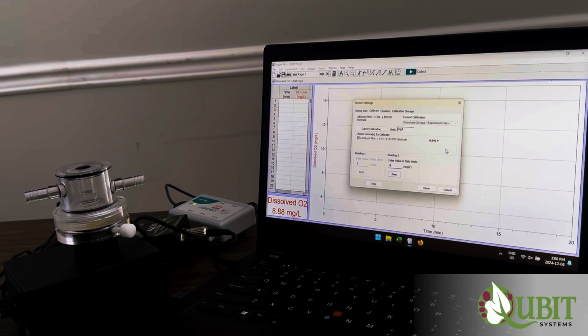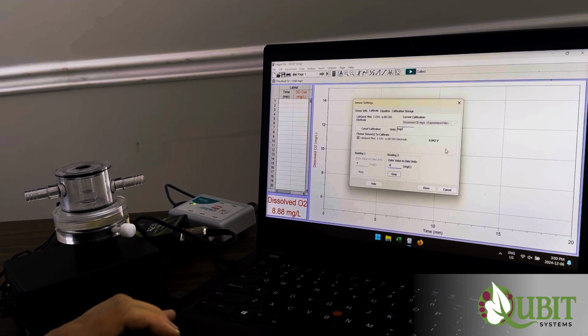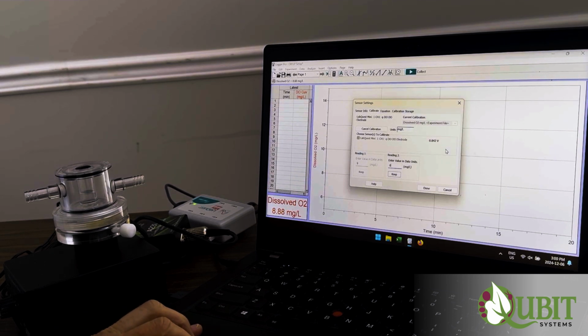And it's really important that you recalibrate the electrode every single time you set it up. Setting up the electrode at the beginning of the day of experiments is a good idea. Leaving it overnight once set up is possible, you know, with some distilled water. But if the next morning you come in and you find your readings are not very stable, erratic in any way, then we recommend that you disassemble the electrode, assemble it again, and recalibrate.